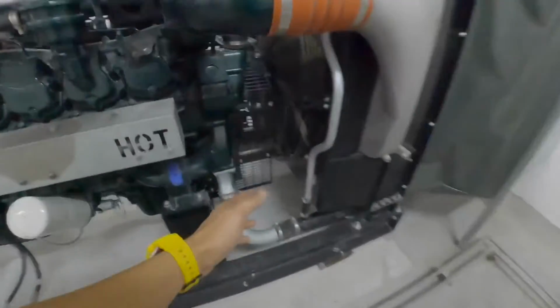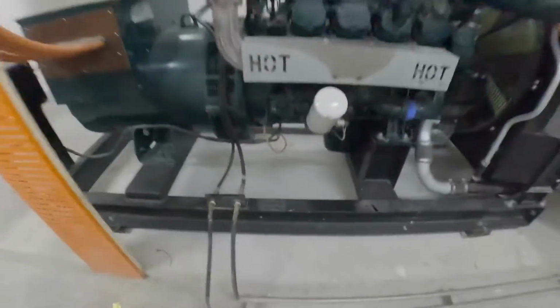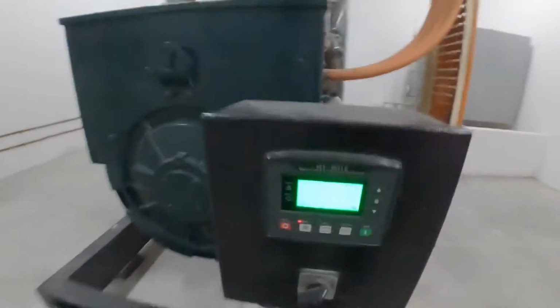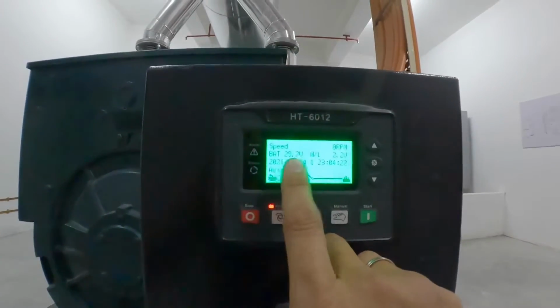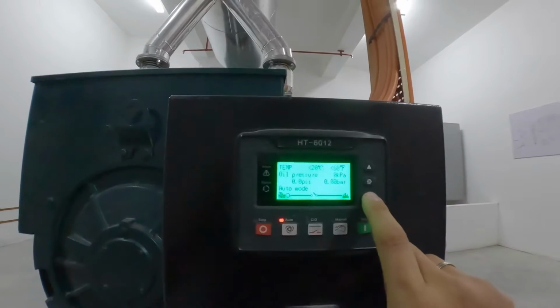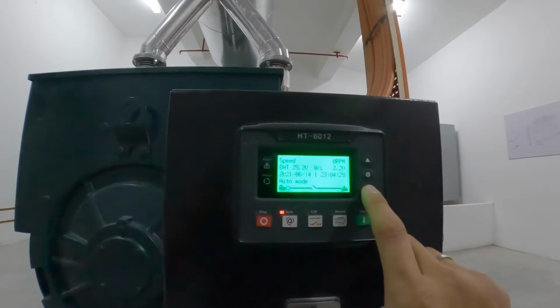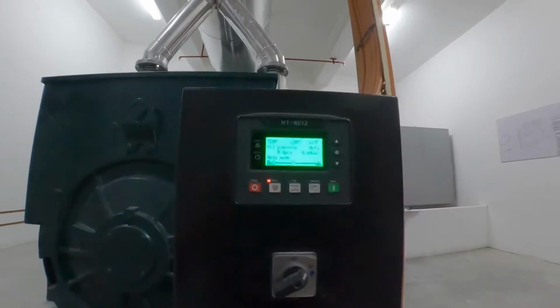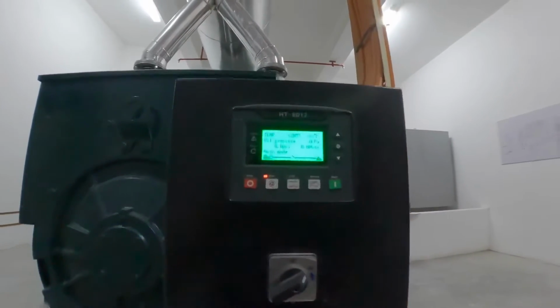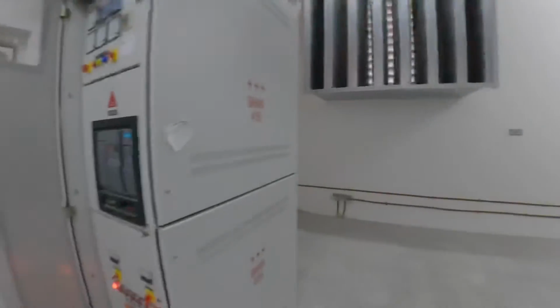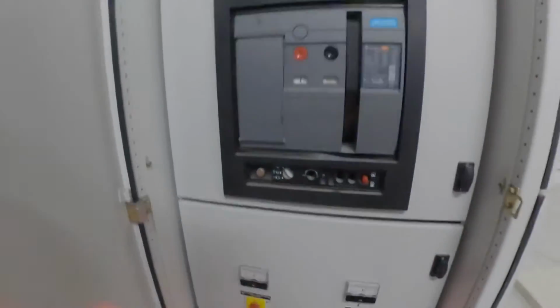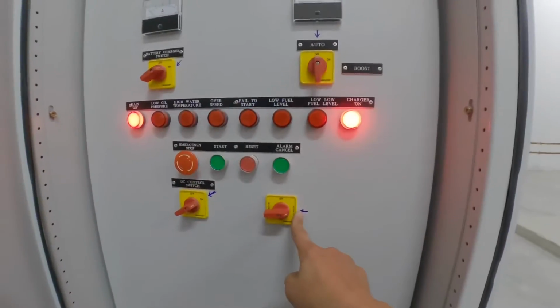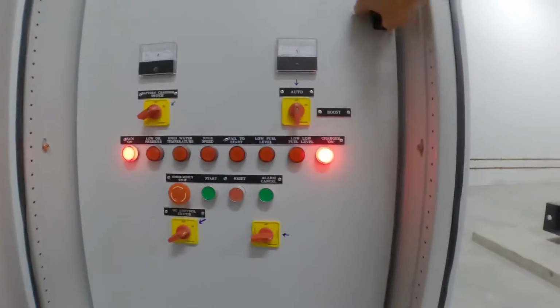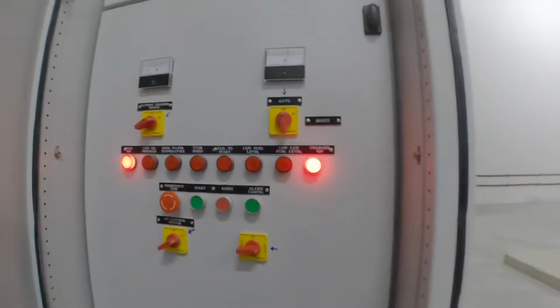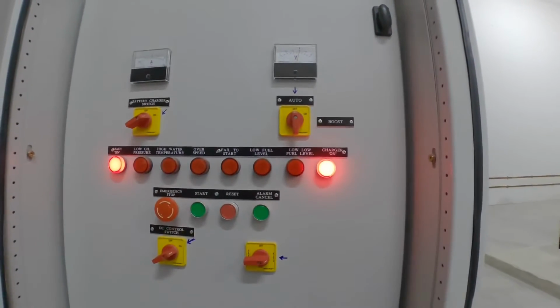Before we test run the genset, always make sure there's no radiator water leakage, no engine oil leakage and no fuel leakages. Let's take a look at the battery. Current battery reading is 29.2 volts. We're going to test the genset one time from here and allow it to stop, and then one more time test it remotely through the ATS panel. Make sure ACB is always on. Current status is auto mode. Chargers are all on, in good condition. We are going to test it using the test mode.